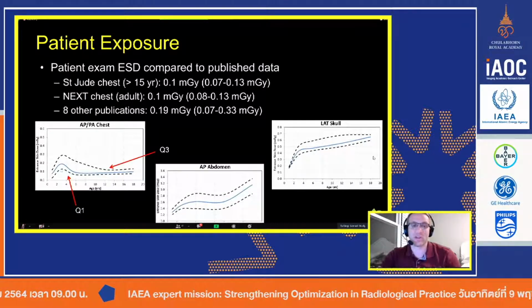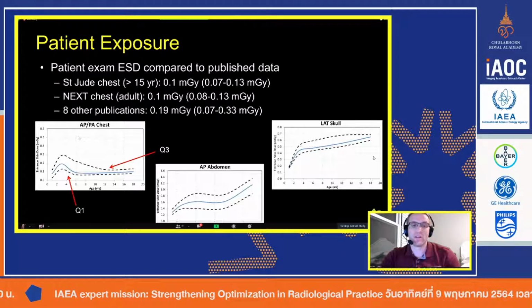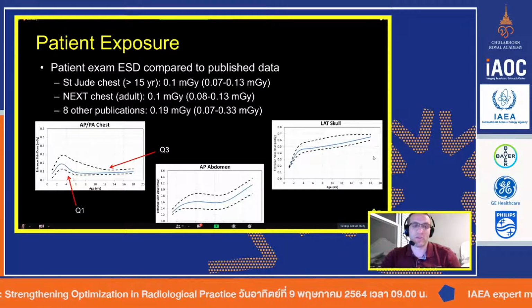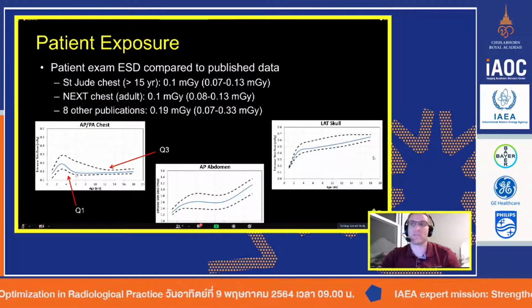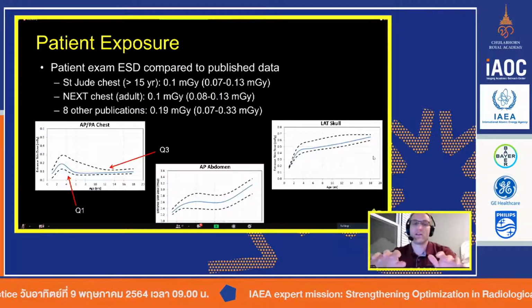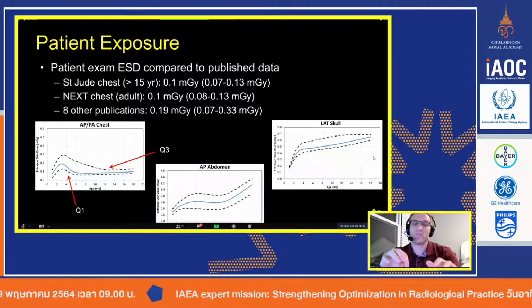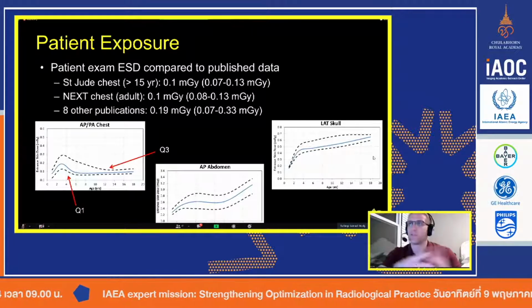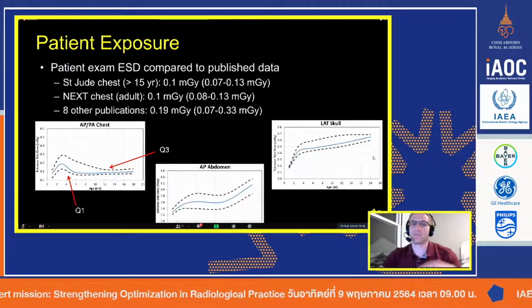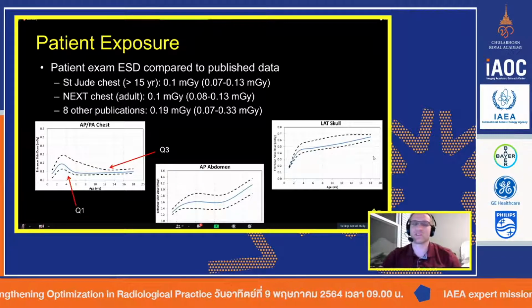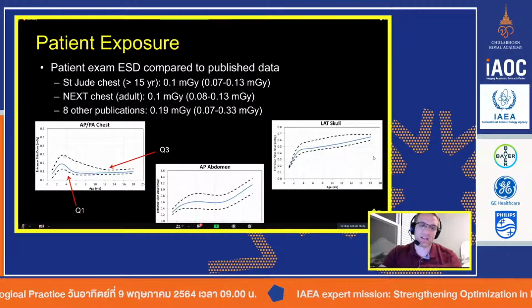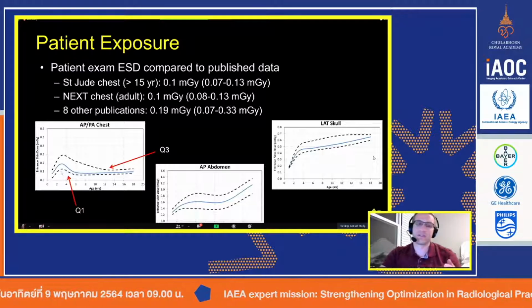This was actually how I found that for the APPA protocols in our patients that were being imaged basically under 6 years old, the values, the KV value, the dose to the detector was incorrect. And I did not know that based on just some of the other values that we were getting out, the EI numbers, because the system thought it was accurate, but it was actually the calibration factor that needed to be adjusted. And so if this number right here is slightly higher, slightly lower for some patients, that's okay.